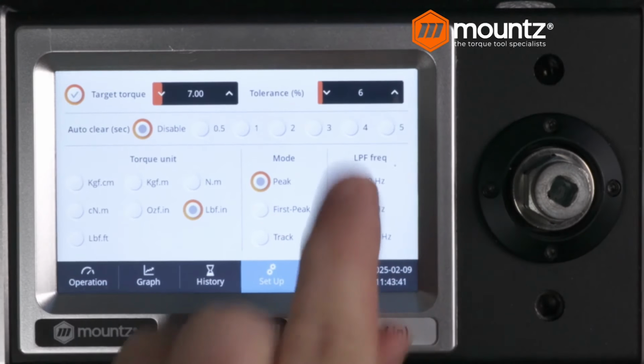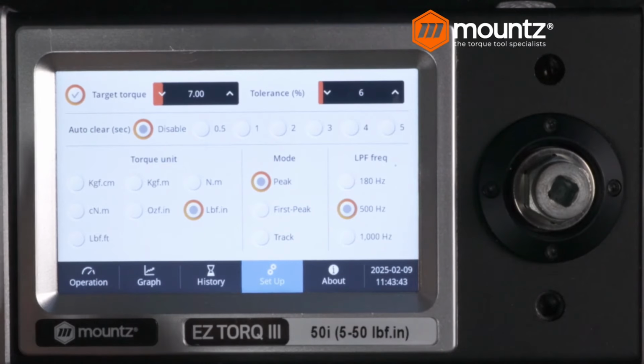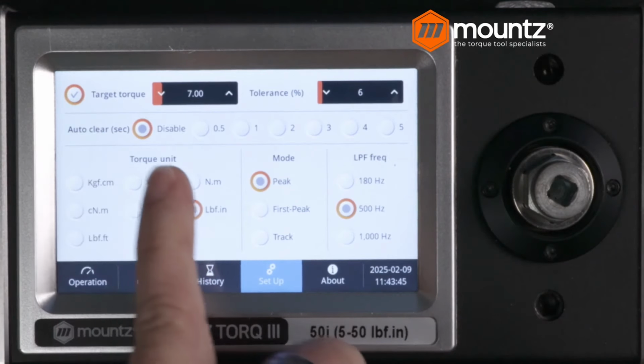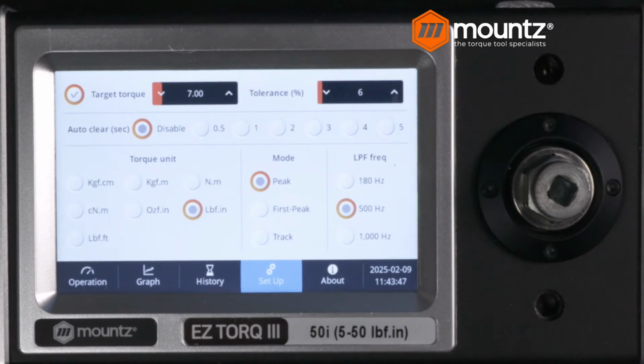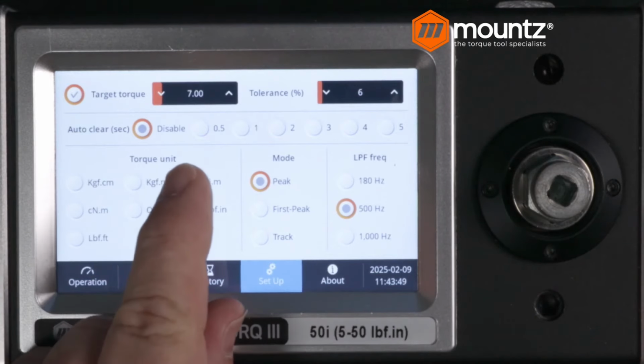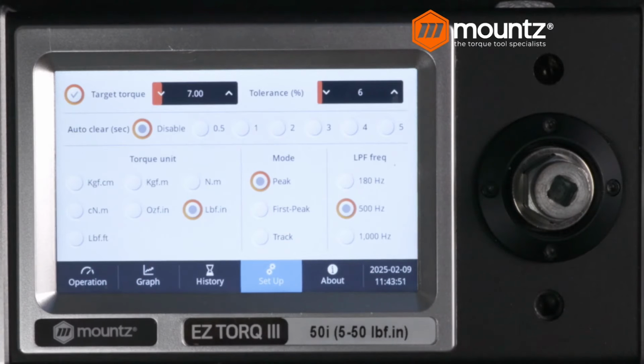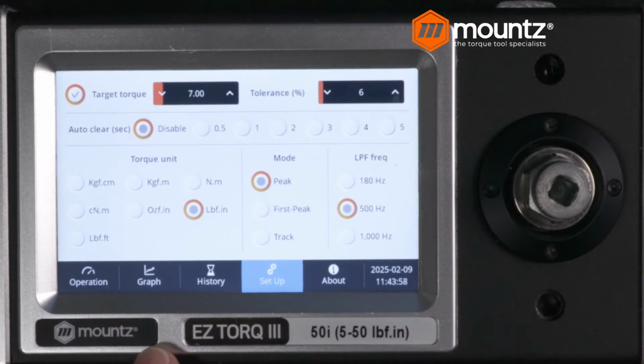And as we are taking readings, we can have those readings automatically clear if we want. Currently it's disabled, but we could have them automatically clear anywhere from a half a second all the way up to 5 seconds before they would be cleared. You have your torque unit of measurement. So we have 7 of those. We'll stick with inch-pounds here.